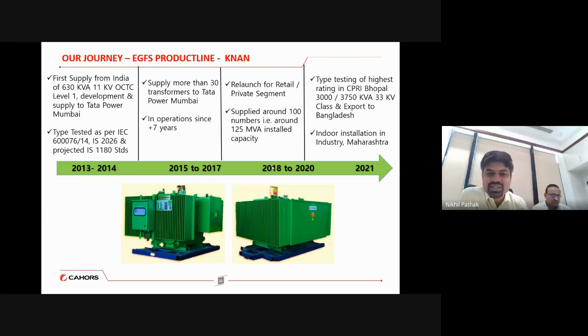And then these practices continued for another 2-3 years, where we supplied more than 30 transformers to Tata Power. Eventually we realized: why are we keeping ourselves limited to Tata Power? We should open this product to the large retail industry and private segment. So after that we relaunched this technology with a formal color code, formal design standards and uniformity, and we have crossed more than 125 MVA installed capacity supplied in this product range. The further development is that our topmost supply rating of 3 MVA capacity has already been type tested at CPRI, and we exported it to Bangladesh in 2021.